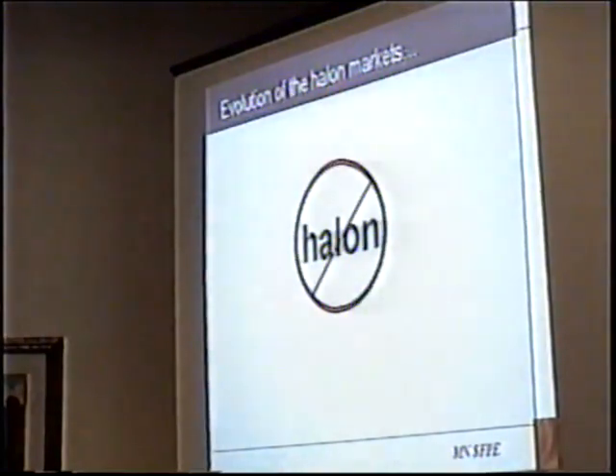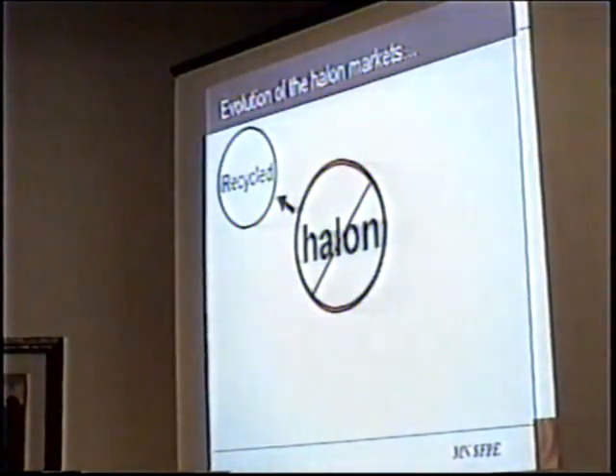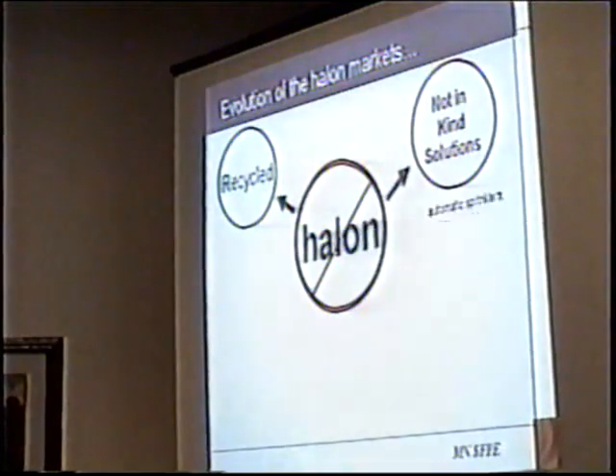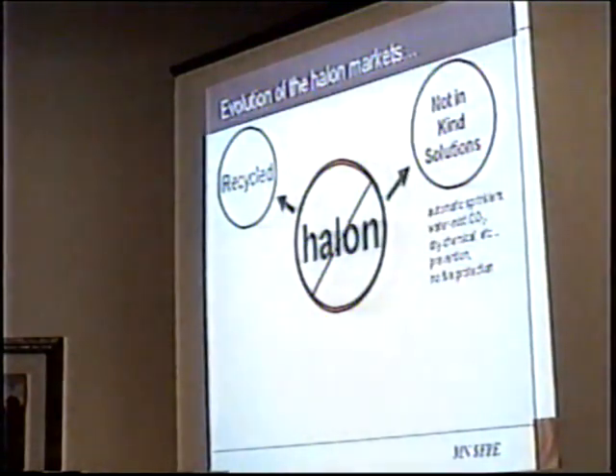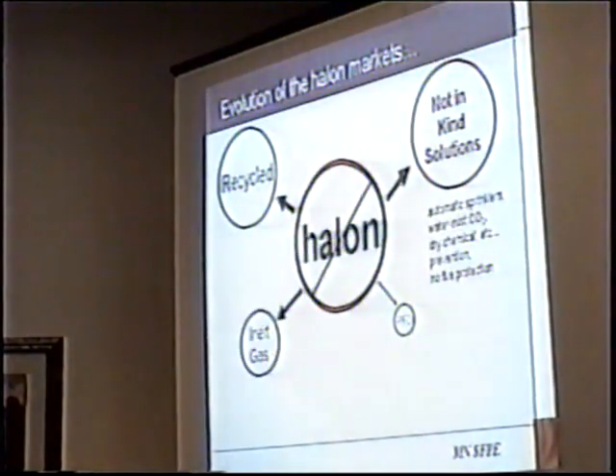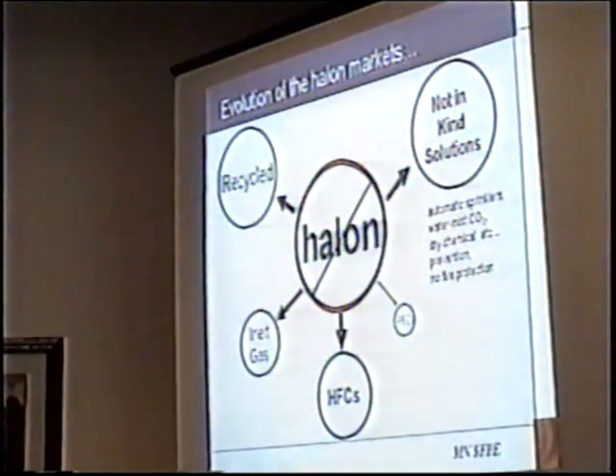So, halon, we banned it. It went in a lot of different directions. Recycled halon. We had not-in-kind solutions, sprinklers. We sold a lot of control systems with sprinklers, where halon was used in the past, or competing with halon. Water mist, CO2, other no protection, prevention, and good sound practices. PFCs were used a little bit, and they were banned pretty much in the late 90s. Inert gases, we talked about that for a little bit. HFCs were pretty much the lion's share in the 1990s to replace halon.